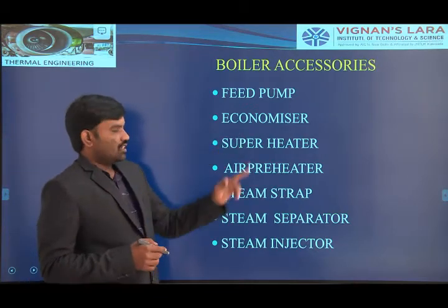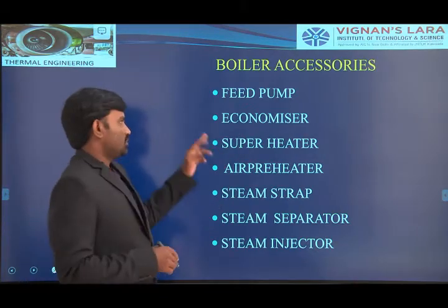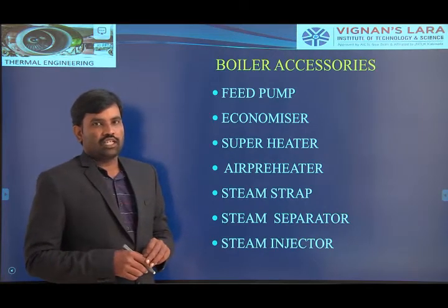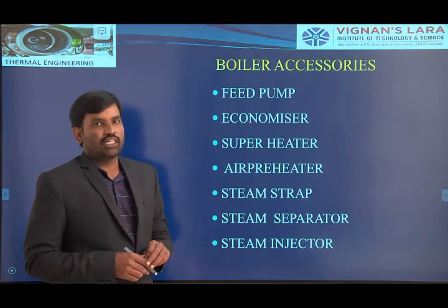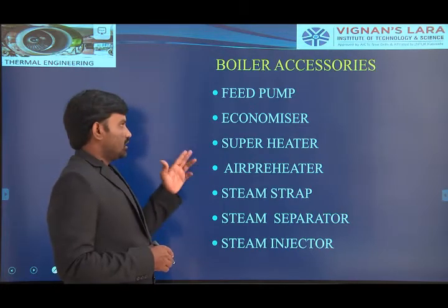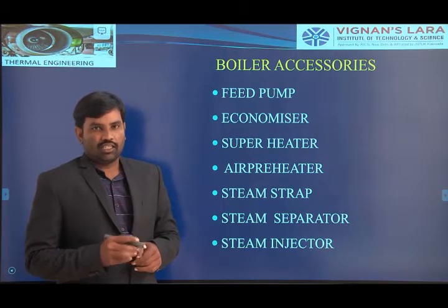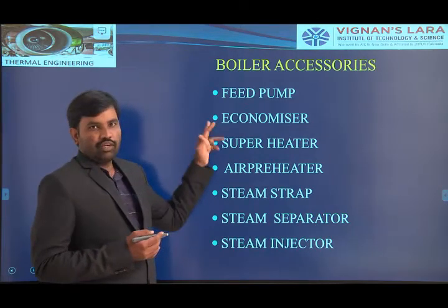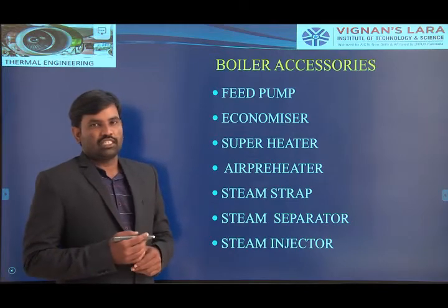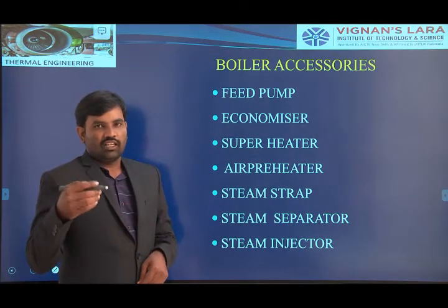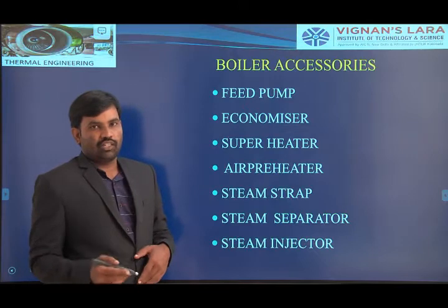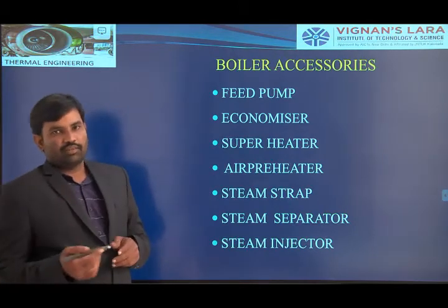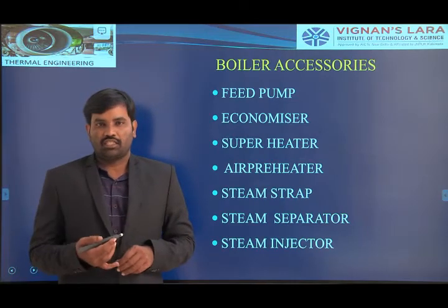The second one is the economizer section. In the economizer section, we heat the feed water up to near the saturation temperature, and we do not generate steam in the economizer section. Water at saturation temperature requires only a smaller quantity of heat. In that manner, we are reducing the heat requirement, so we can increase the efficiency of the boiler.